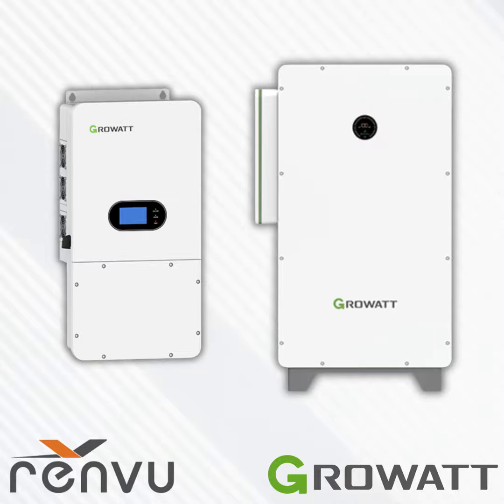And this is an introduction to our SPH 10K inverter. Again, dustproof, waterproof. It's got a built-in integrated transfer switch, supports 120, 208, and 240 volt split phase output. NEMA 4X rating. And again, supports a larger variety of generators and can be paralleled up to 6 units, with a huge battery capacity, up to 160 or even 320 kilowatt hours. This is the ALP battery, 48 volt, that pairs with the SPH. And Luke is going to talk about this a little bit more in depth soon here.